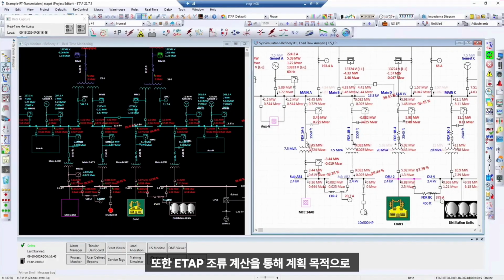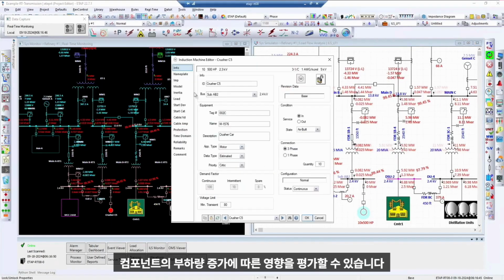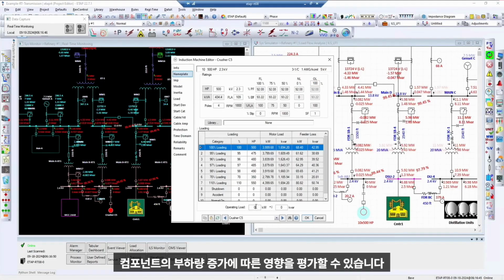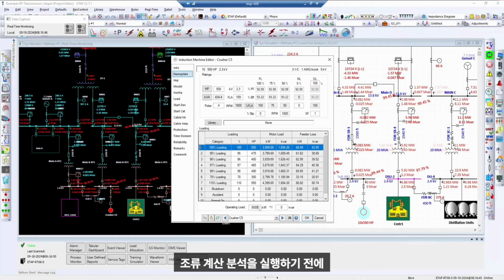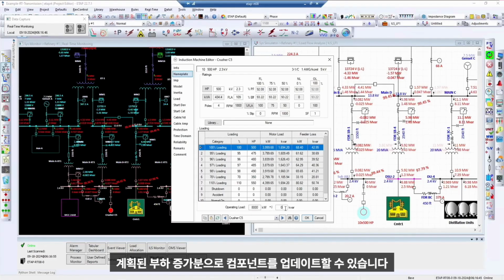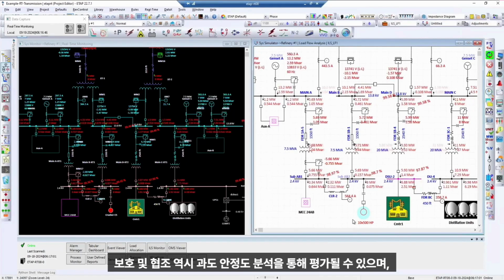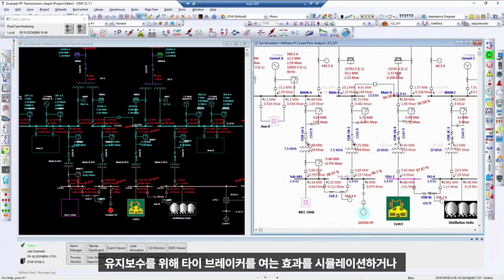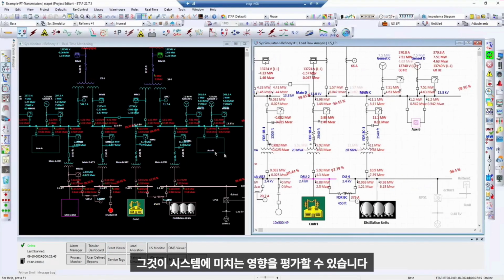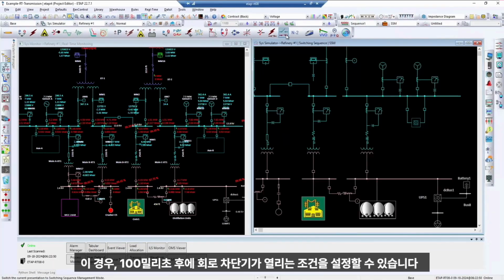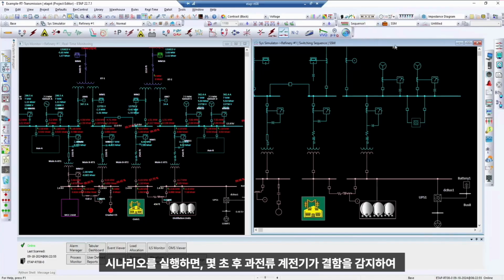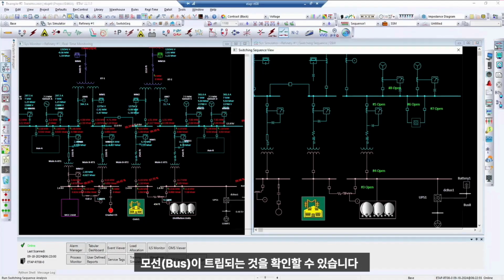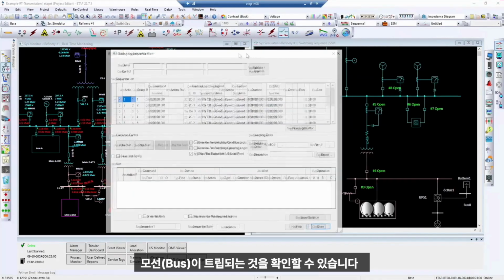Using ETAP load flow, I can also evaluate for planning purposes the effect of increasing the amount of load in a component. Before we run the load flow analysis, we can update the component with the planned increase in load. Protection and coordination can also be evaluated using transient stability, where I can simulate the effects of opening a tie breaker for maintenance or evaluate how it will impact the system. In this case, we can set up a condition where after 100 milliseconds, the circuit breaker is open. Once we run the scenario, we can see that after a few seconds, the bus will be tripped because of an overcurrent relay detecting the fault.